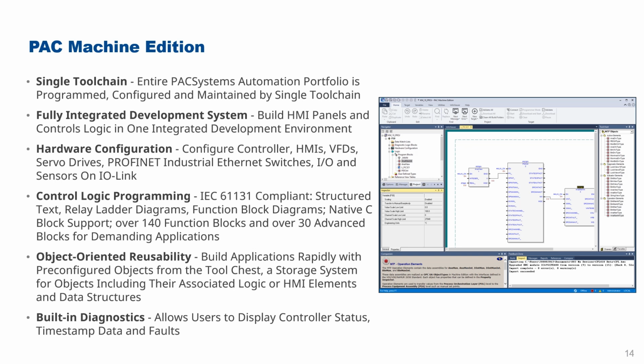We also have tools for configuring the controller, the HMIs, as well as variable frequency drives, servo drives, Profinet industrial switches, and including remote I/O and the IO-Link devices. Control logic programming is supported using IEC 61131 Part 3 languages, including structured text, relay ladder diagrams, and function block diagrams. We also have native C block support, allowing high-speed routines to run directly on the hardware, compiled from a standard compiler, and allowing very high performance, as well as protecting intellectual property.